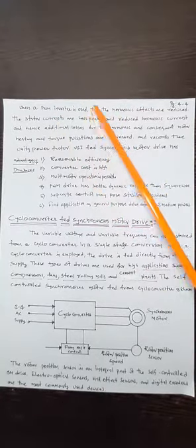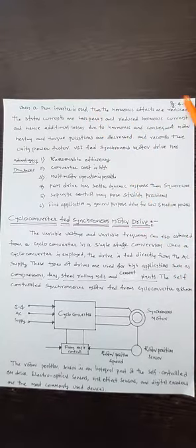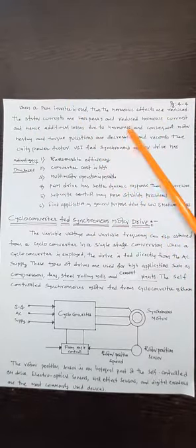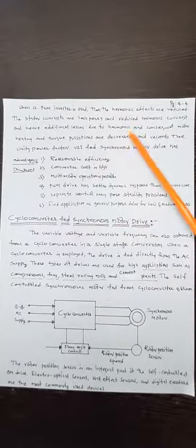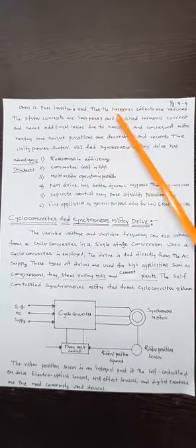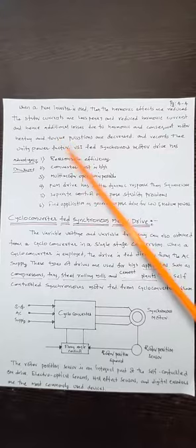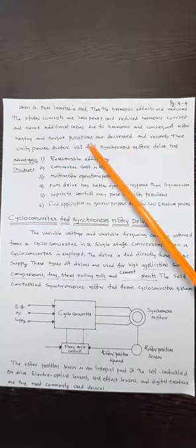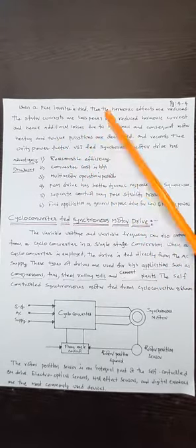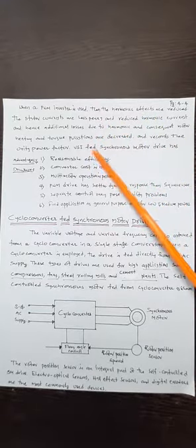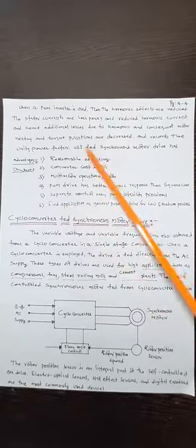The stator currents are much less peaky with reduced harmonic current, and hence the additional losses due to harmonics and the consequent motor heating are reduced. Torque pulsations are drastically decreased. This is the speciality of the PWM inverter compared to the square wave inverter. And regarding unity power factor, if the machine is operated with over-excitation, the synchronous motor definitely operates at unity power factor. So the VSI fed synchronous motor drive has its specialities, its advantages and drawbacks, which are covered here.